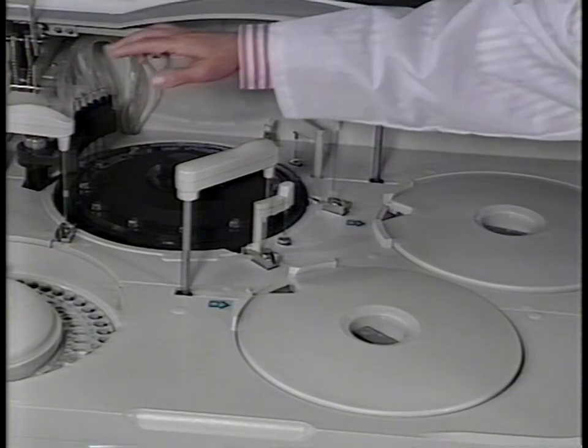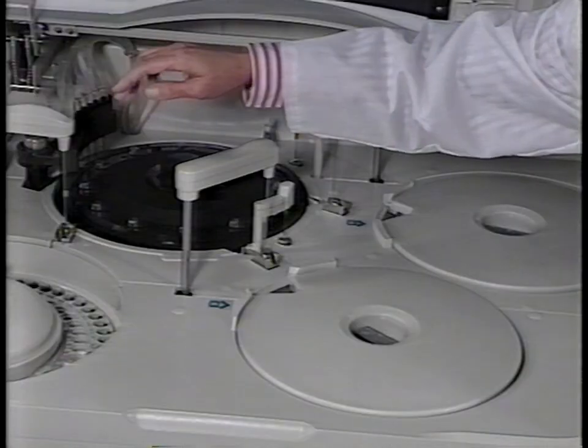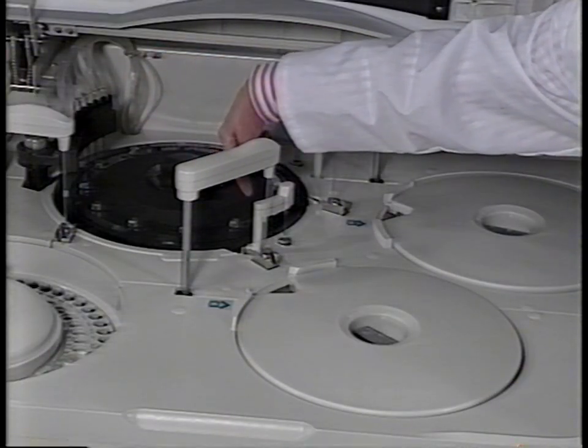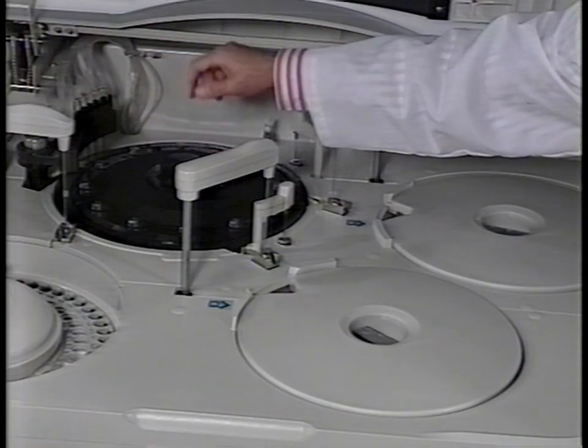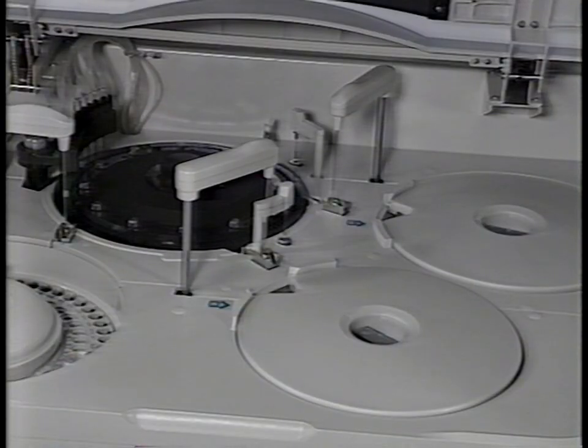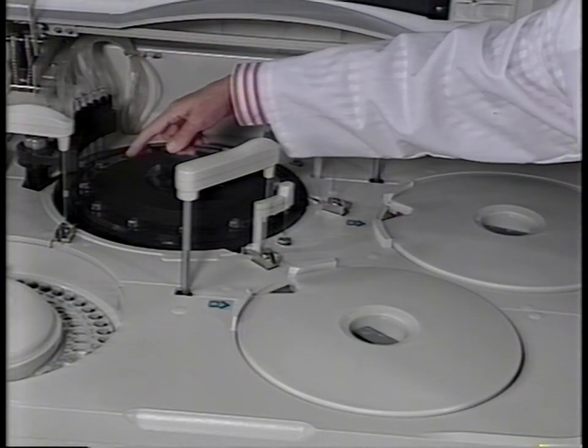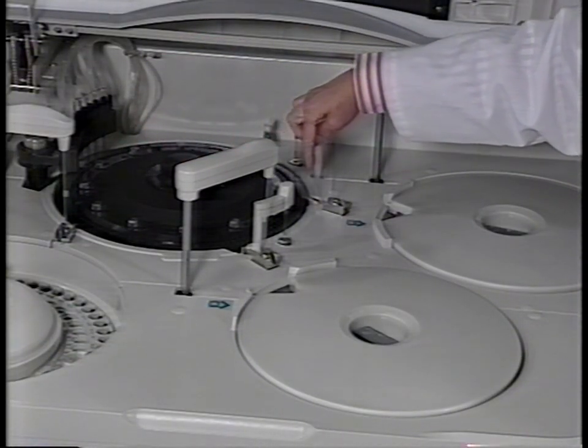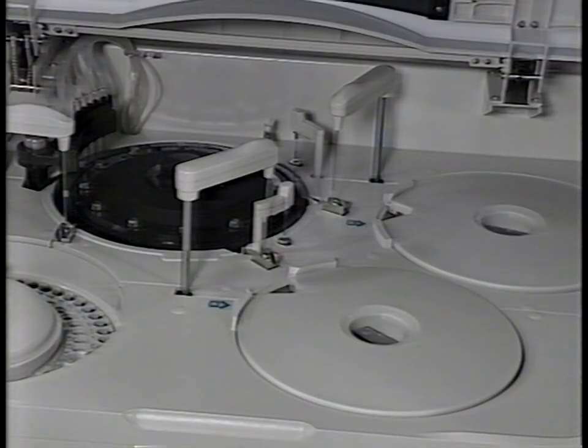The sample probe dispenses sample into the cells of the reaction disk. Each cell is automatically cleaned and blanked before it is used for sample dispense. After a cell receives sample, the reaction disk rotates it to a position where reagent is added, then moves it past the photometer for the absorbance readings.